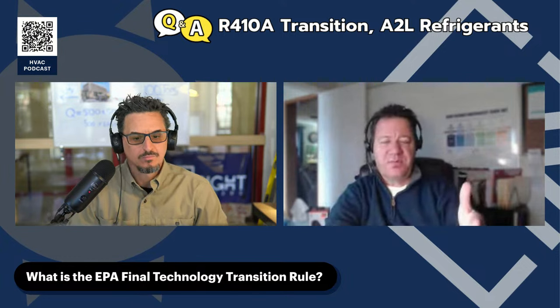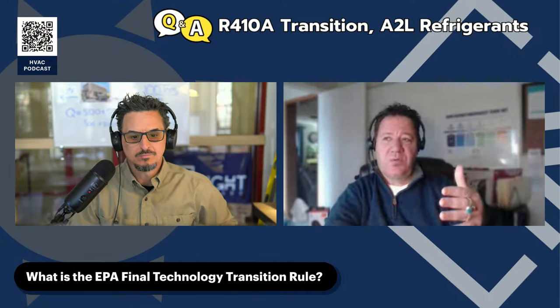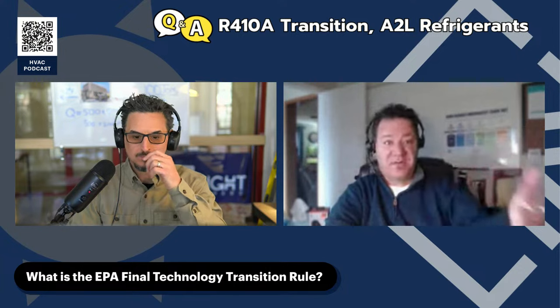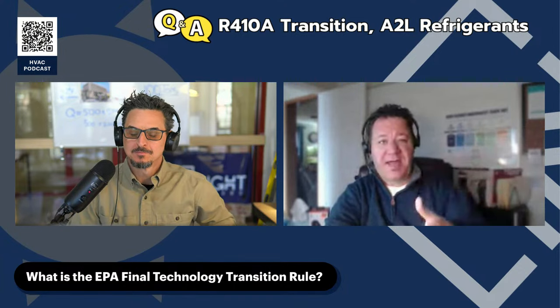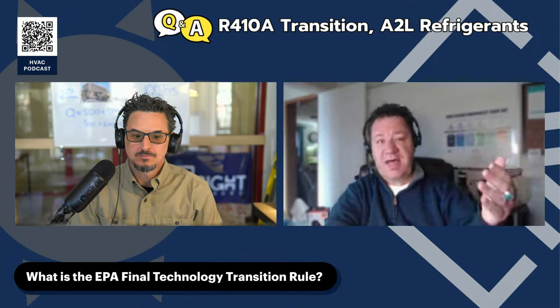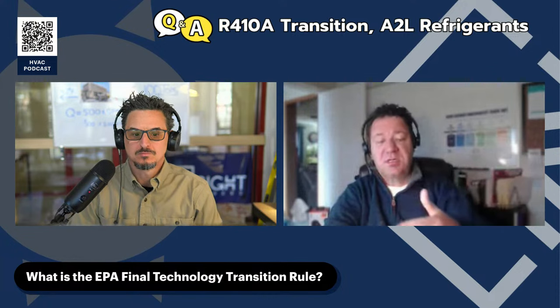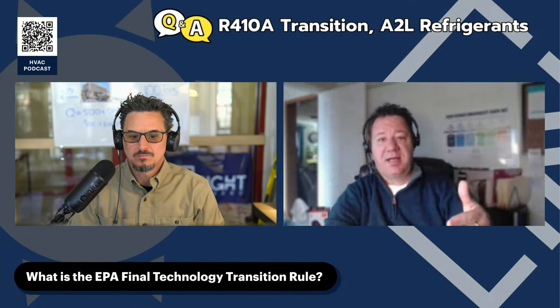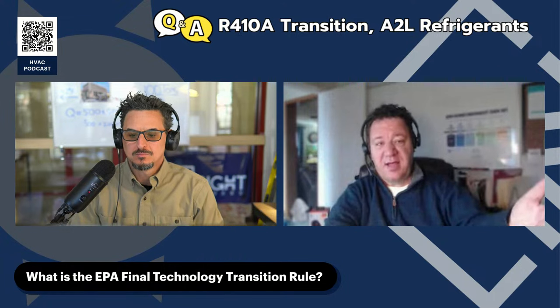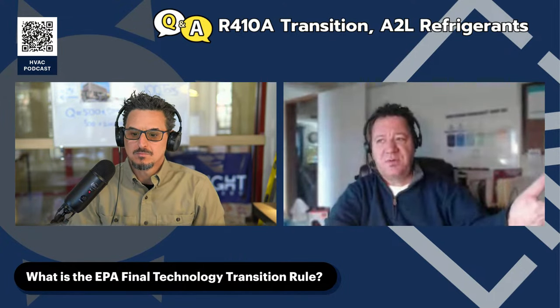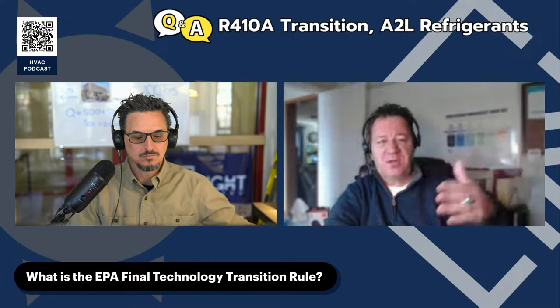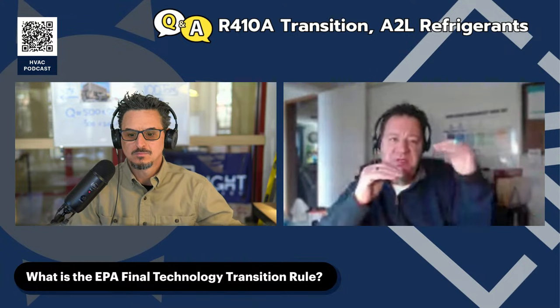We have 454B for air conditioning, that's less than 700, as we talked about. We have a 454A and a 454C. The 454A has a higher GWP, so that will be for the lower than 200 pounds category. The 454C has a lower GWP, so that'll be the less than 150 pounds category. And when I say lower, they're way lower. The 454A, for example, is 238, so it's way below that 300.